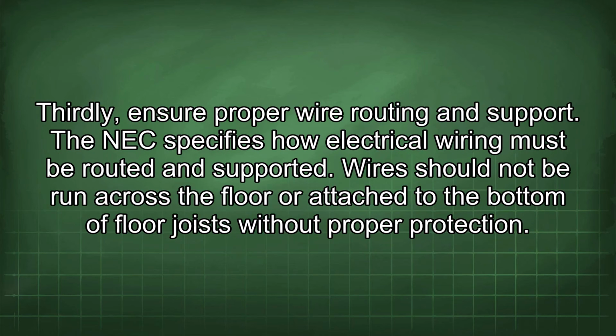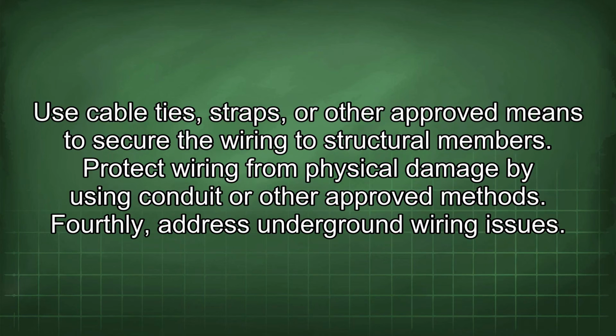Thirdly, ensure proper wire routing and support. The NEC specifies how electrical wiring must be routed and supported. Wires should not be run across the floor or attached to the bottom of floor joists without proper protection. Use cable ties, straps, or other approved means to secure the wiring to structural members. Protect wiring from physical damage by using conduit or other approved methods.